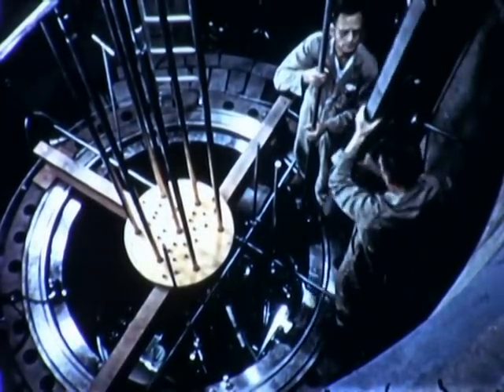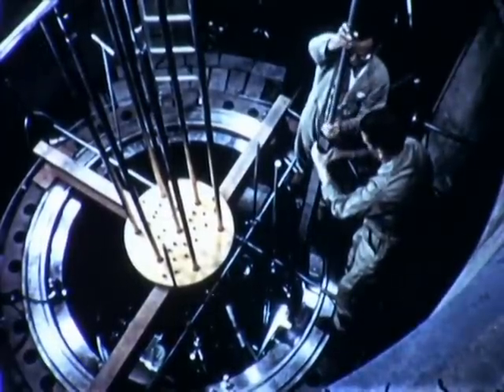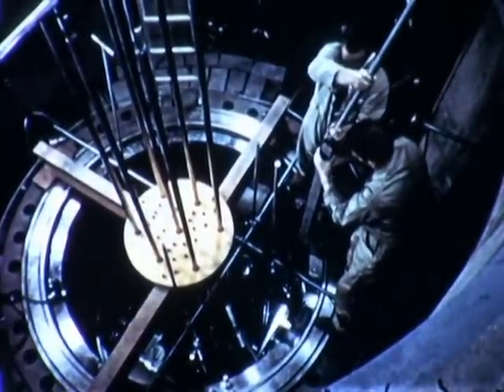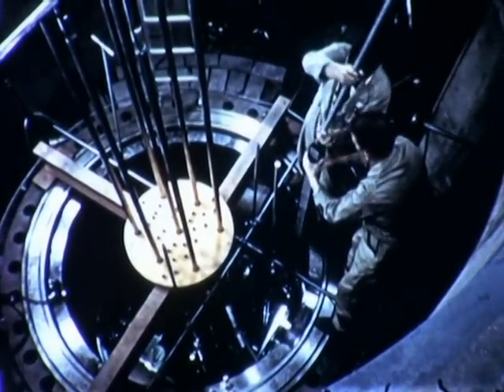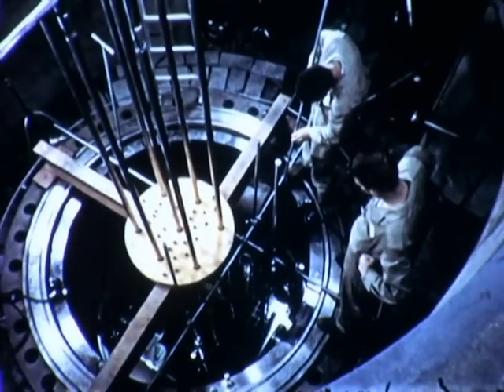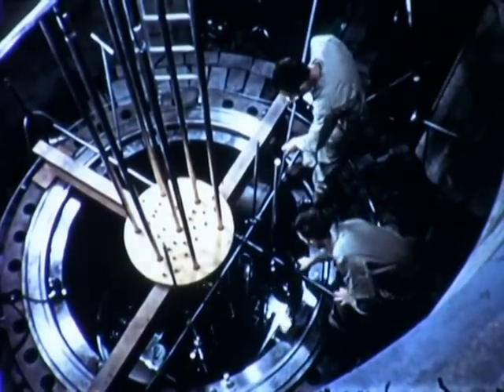Experience with this developmental reactor, the Argonne EBWR and Borax 4, indicates that Dresden's high operating pressures, forced circulation system, relatively long fuel element time constant, low ratio of incremental reactivity of voids to incremental void volume, and close regulation of reactor system pressure eliminate any problem of instability. In addition, the Vallecitos plant is being used to test Dresden fuel elements and as a training center for personnel who will ultimately operate the Dresden station.